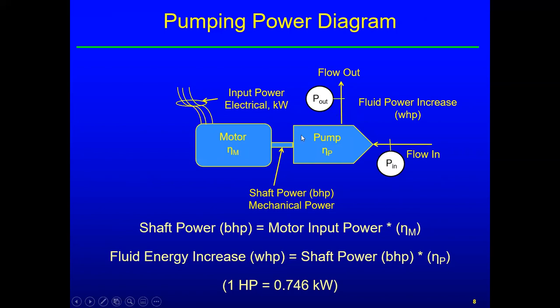In pumping analysis, we typically calculate pump efficiency by measuring pressures and flow rate to get water horsepower, then taking an electrical measurement and looking up motor efficiency at the operating load to get brake horsepower. The ratio of water horsepower to brake horsepower is the calculated pump efficiency. The PSAT program — sponsored by the US DOE — and its newer version called MEASUR both help with this. The PSAT program has been translated and is accessible through MEASUR, and we'll see screenshots of that.